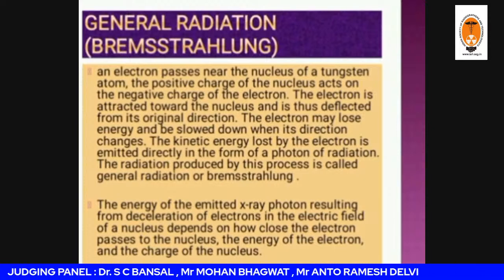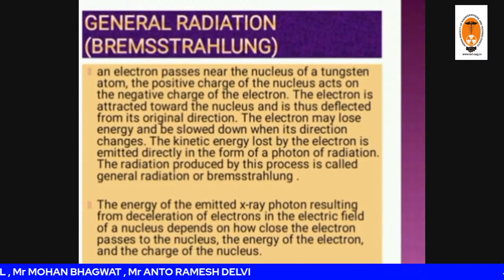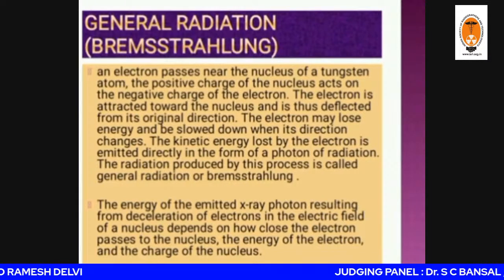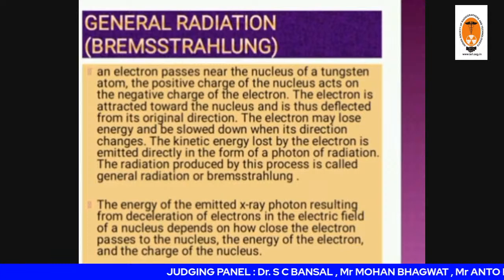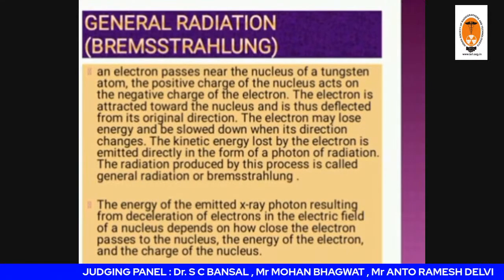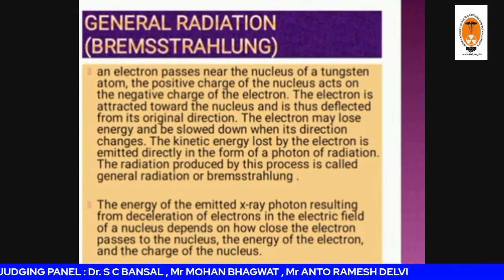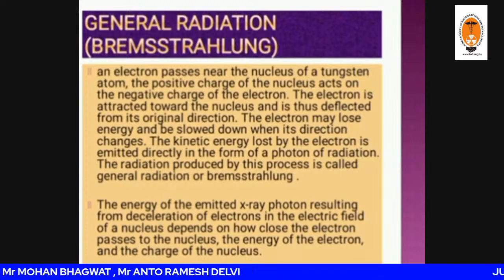The amount of bremsstrahlung X-ray production is determined by the distance between the bombarding electrons and the nucleus. Suppose the electron is at a very large distance, hence the Coulombic force is weak, and low energy X-rays are created, and this has a higher probability of occurring. Second, when the electron is at a very close distance, the Coulombic force is strong, higher energy X-rays are created, and this has a lower probability of occurring.